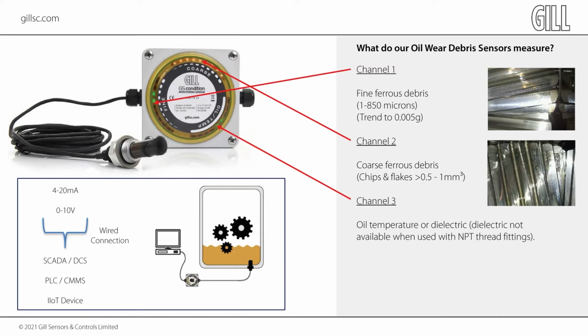The Gill WearDetect sensor allows operators to capture and trend the wear rate of contacting surfaces that are ferrous in nature by simply replacing the existing drain plug with our magnetic sensor probe. The sensor requires a DC power supply, typically 12 or 24 volts.